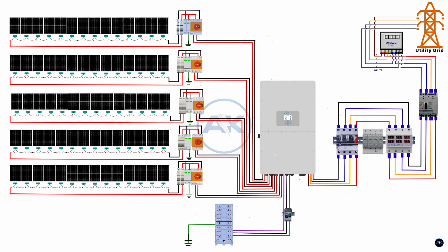The isolator must disconnect all three phases and neutral. Connect the meter output to the AC isolator input, matching L1, L2, L3, and neutral. The isolator output will feed the next protection device.